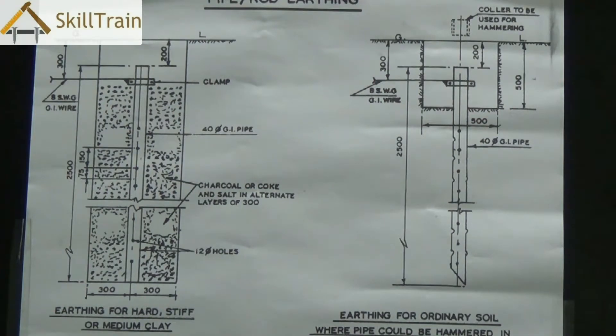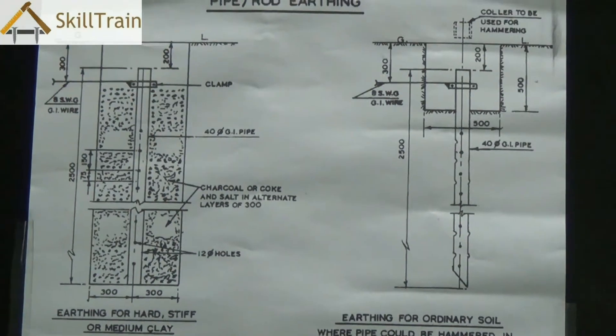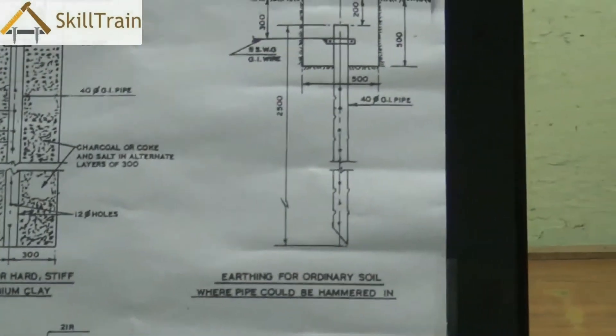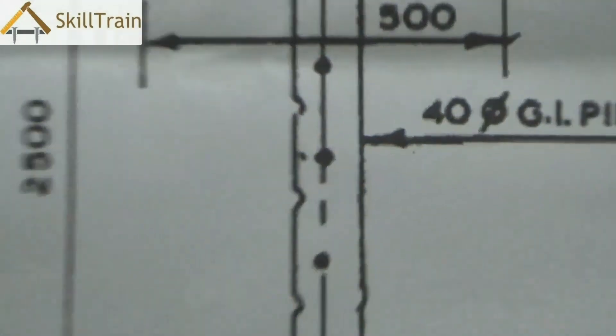These are very thick wires which are used to dissipate electricity back to the earth. For a hard surface you may need to dig a pit for about six to seven feet where the GI pipe is placed underneath along with the charcoal and salt mixture.